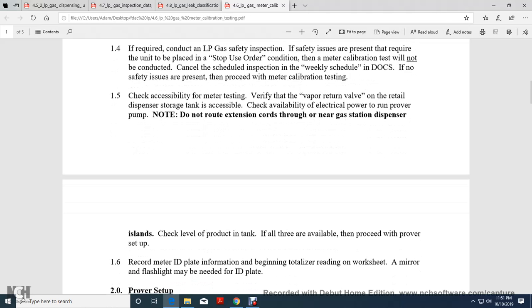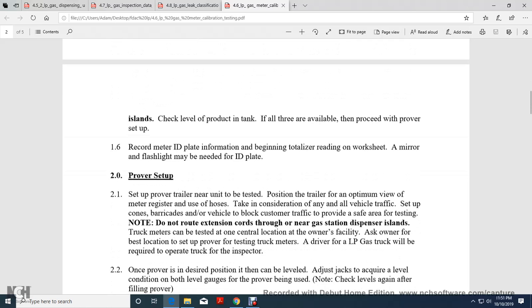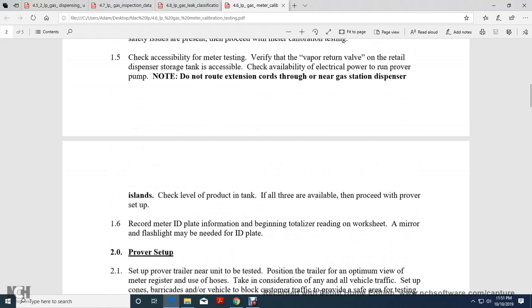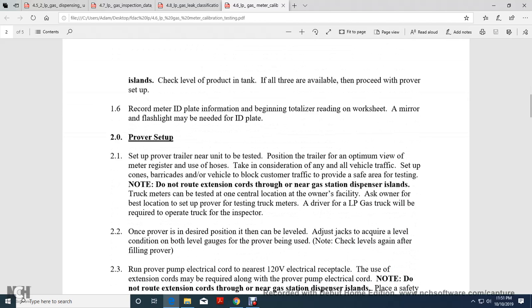Check accessibility to verify that the vapor return valve on the retail dispenser storage tank is accessible. Check availability of electrical power to run the prover drum pump. Do not route the extension cord through or near gas station dispenser islands. Check the level of the product in the tank. If there is enough available, proceed with setup. Record the meter ID plate information, beginning with the totalizer reading, on the worksheet. A mirror and flashlight may be needed for the ID plate.